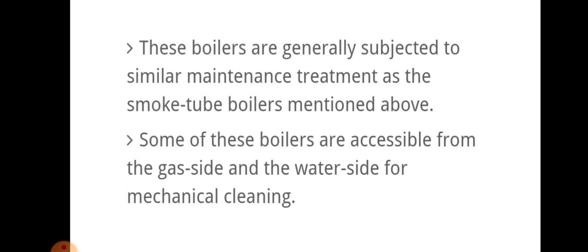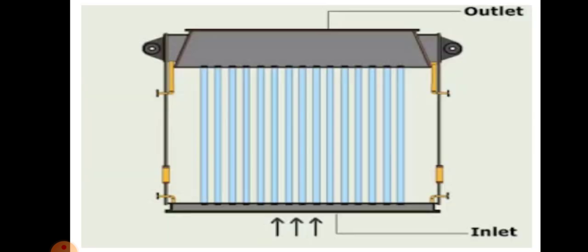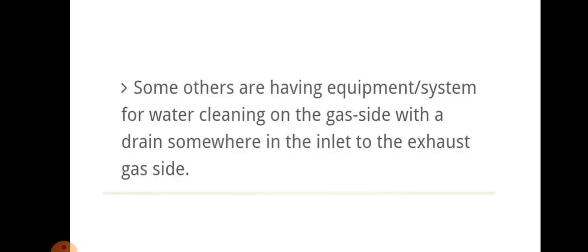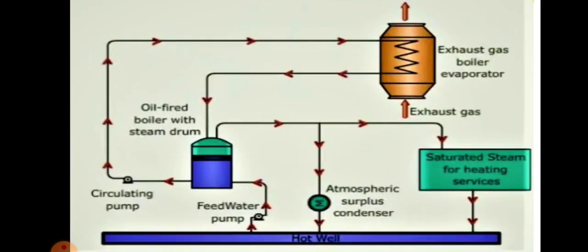Some of these exhaust gas boilers are accessible from the gas side and water side for mechanical cleaning. There will be outlet and inlet as shown. Some others have equipment or a system for water cleaning on the gas side, with a drain somewhere in the inlet to the exhaust gas side.